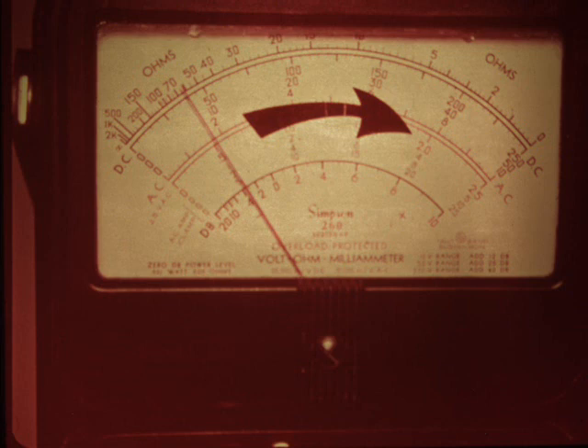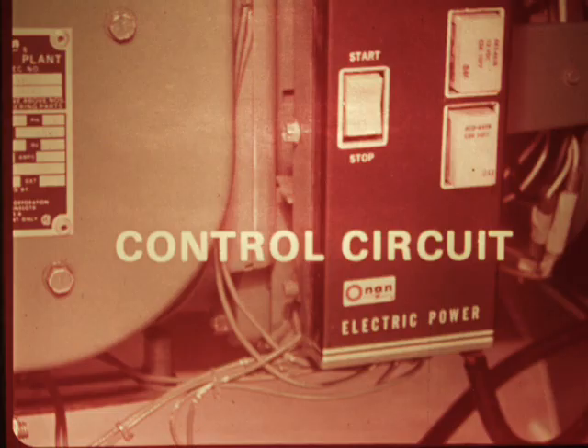Check the ignition system and set the timing to 25 degrees before top dead center. To test the compounding reactor, measure the field voltage in load and no-load conditions. If a load doesn't boost reactor output to the field, the reactor must be replaced.